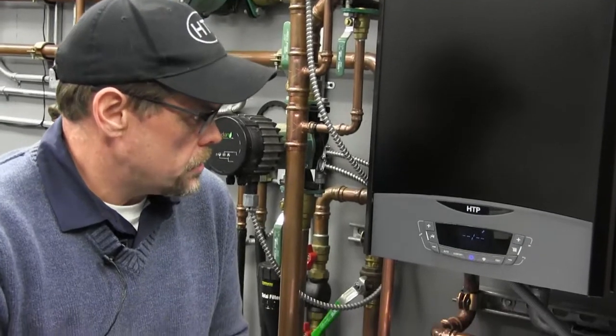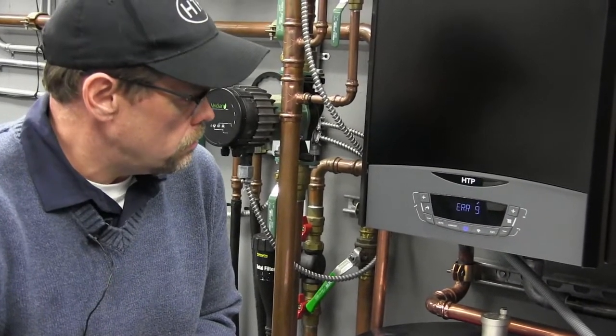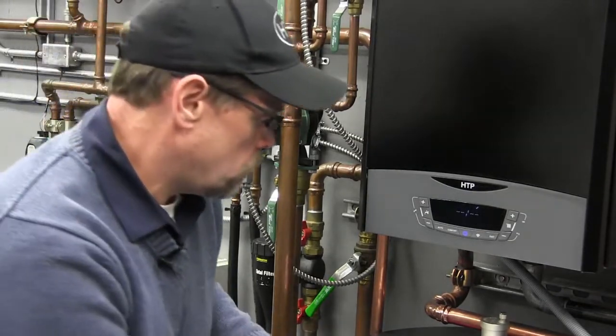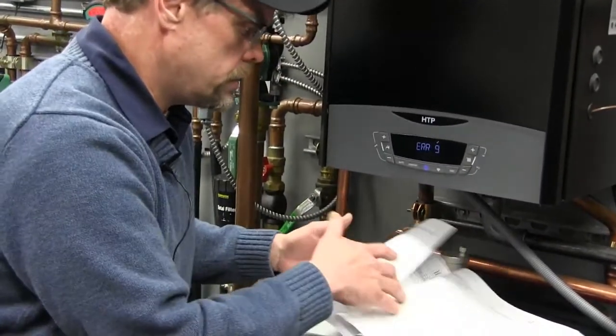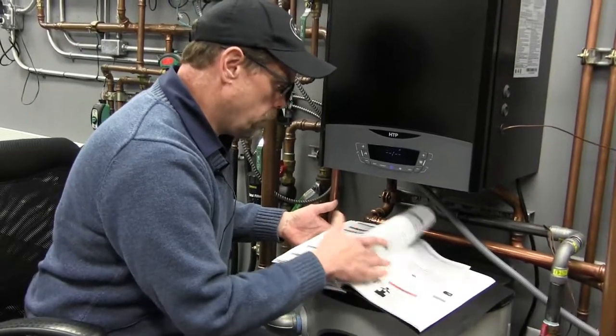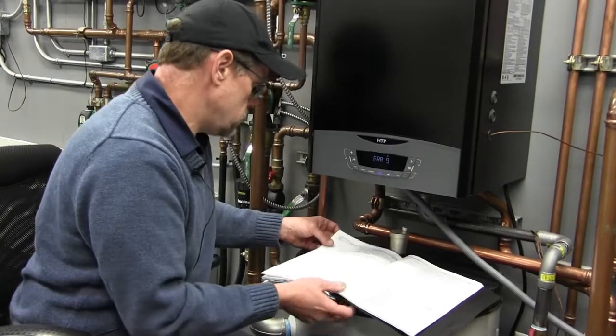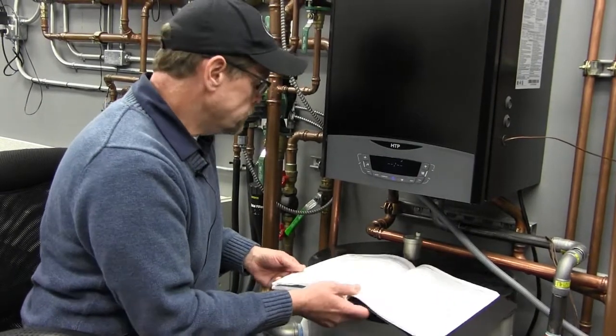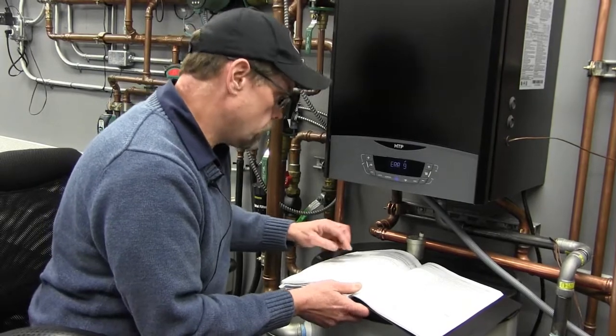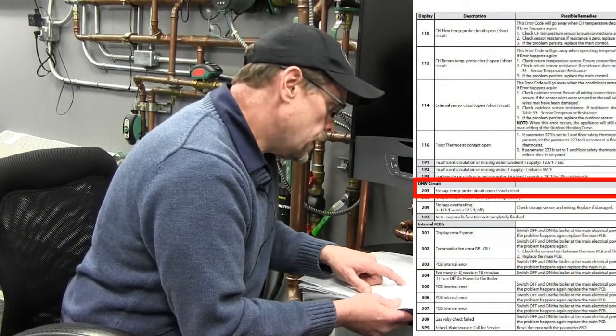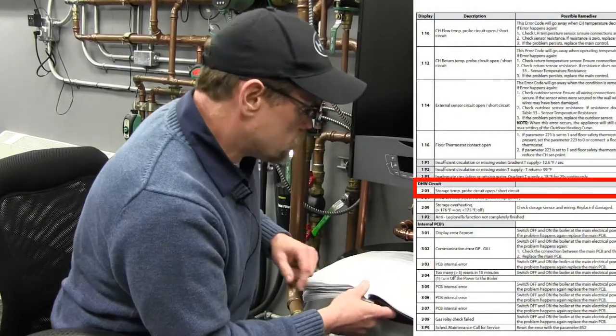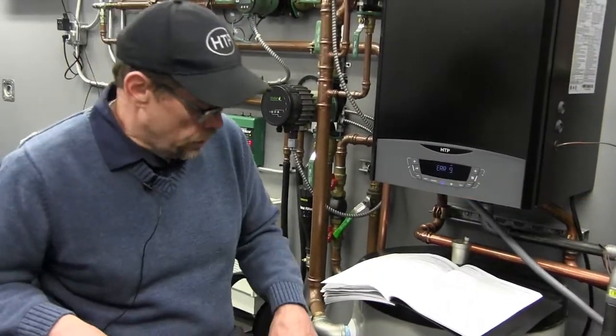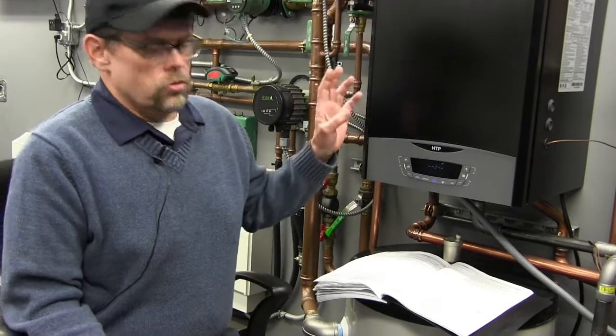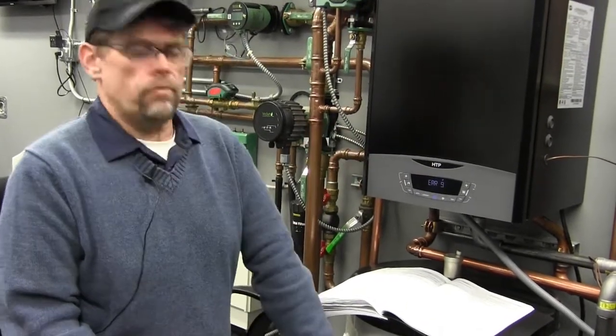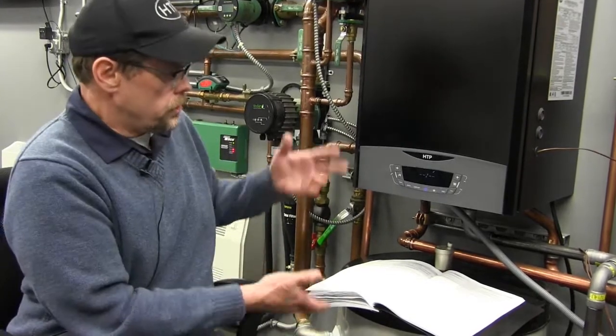And in this particular case, it's telling us that the 9th error code is 203. So what I would do to find out what 203 is, go into my install manual and find the error code section here. I'm on page 80. And on page 80, we start to go through and we look for error 203, and I find it over on page 81. And it says that the storage temperature probe circuit was open or short-circuited. And basically all that was is I told the controller earlier in another demonstration that the indirect was going to be operated by a sensor. Well, obviously there's no sensor.